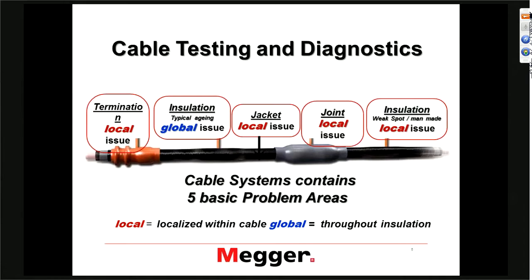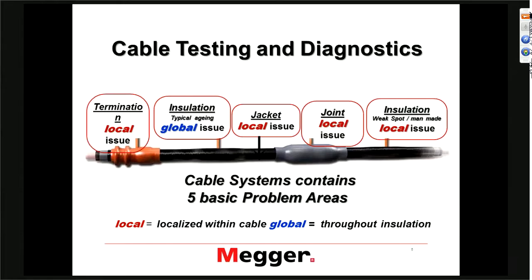Going to the next one, we have the insulation itself — XLPE, EPR, or paper cable, whatever it is. The issue we have to consider there is the aging of the insulation over 30, 40, 50 years. The aging condition is what we call global, because it's typically not limited to a particular area — it's basically the aging of the entire insulation throughout the cable system.